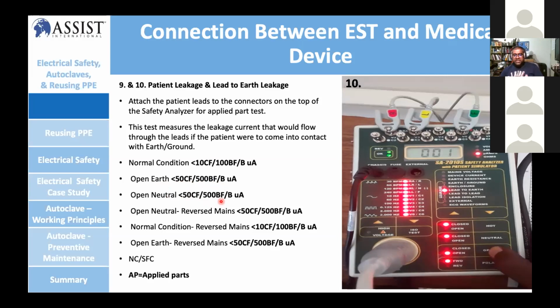So for patient leakage lead to earth, you can do the measurement in group or individually. Sometimes if your lead isolation is not good, you're going to get a reading of more than 10. That means it's quite dangerous to use on the patient. Like this is 1, so it's quite low and safe to use.